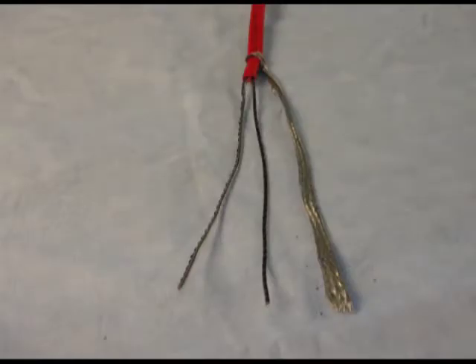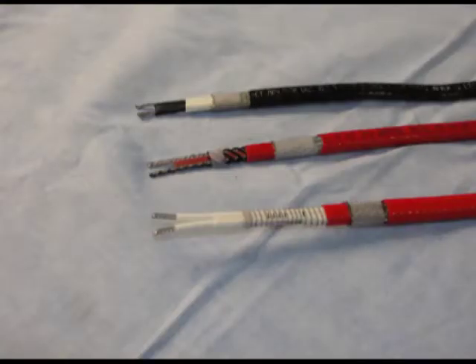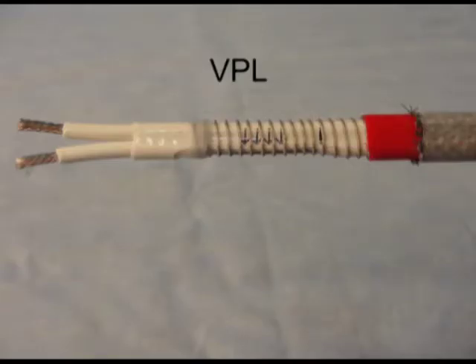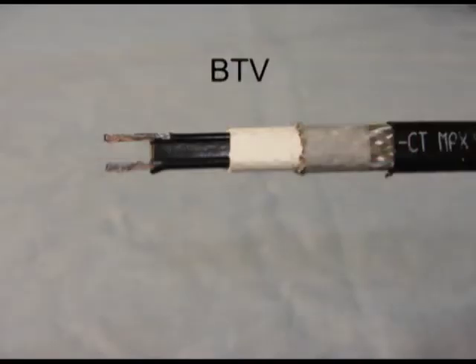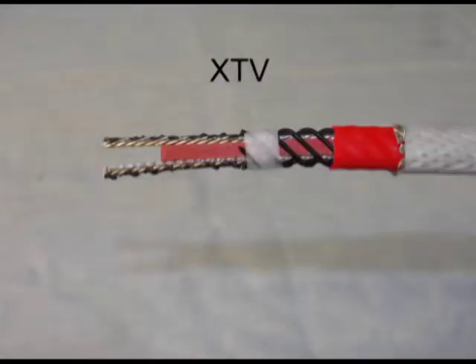Score and remove center spacer. Remove any remaining fiber material from buss wires. Pull the braid tight to make a pigtail. We have shown the procedure for trimming back the Raychem XTV heat tracing product. A different procedure must be followed with alternate heating cables. Shown here are the VPL, the BTV, the XTV heat tracing products from Raychem.